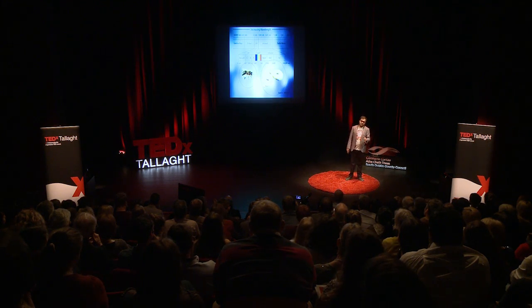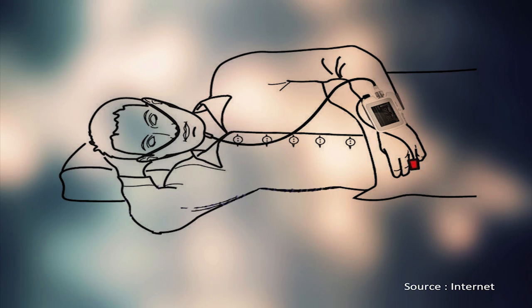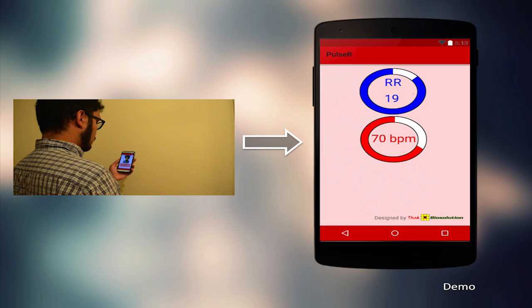Modern medical devices emulate this animal sense by shining light beyond the visible range on the skin. For example, oxygenated blood absorbs more infrared than the surrounding tissue. So a fingertip-based pulse oximeter shines infrared light at the tip of your finger and measures the difference in absorption with time. And this tells it about your pulse.